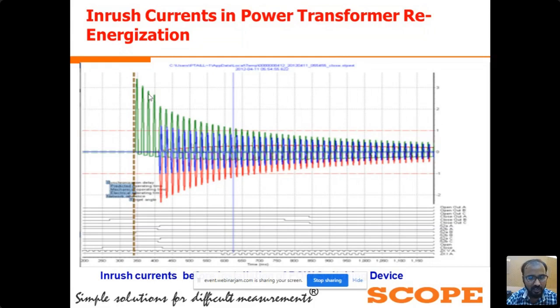Here we can see that for the Y phase the inrush current is more than 3 times the full load current. This is the waveform we recorded for the CSD that we installed at the JETCO substation for the 400 kV system and 500 MVA transformer. The full load current for that transformer is near 700 ampere. We can observe this only on the positive side: the transformer took more than 3 times the full load current as high inrush current.